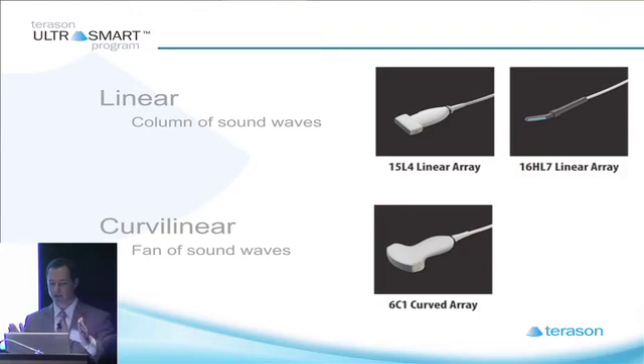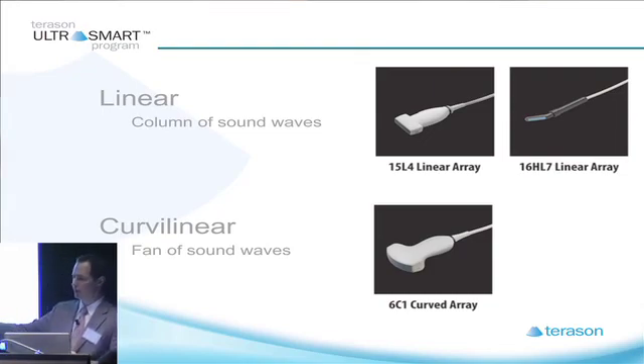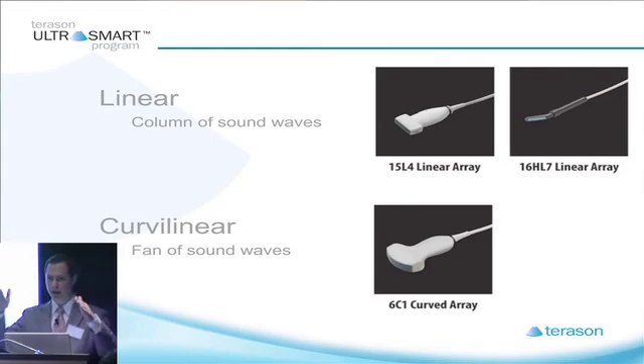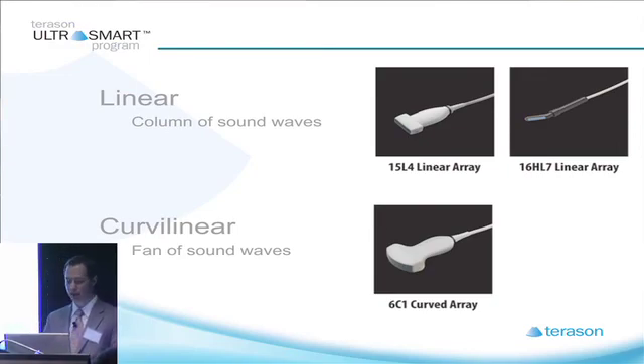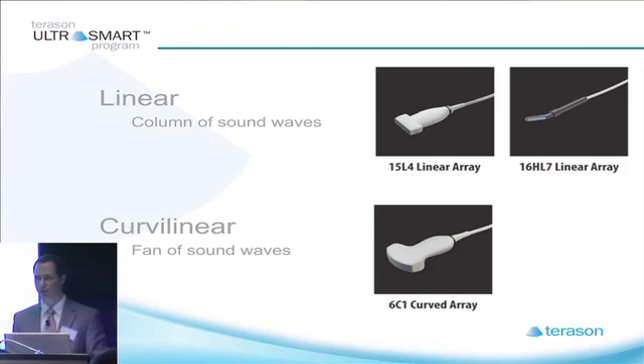Linear arrays send out a column of sound waves, more or less, although there are some features I won't mention much, which include trapezoidal imaging, where a linear array can send out signals beyond the column. The curvilinear sends out a fan of sound waves — the same kind of transducer you'd use for OB purposes or abdominal scanning, which most of us would recognize.